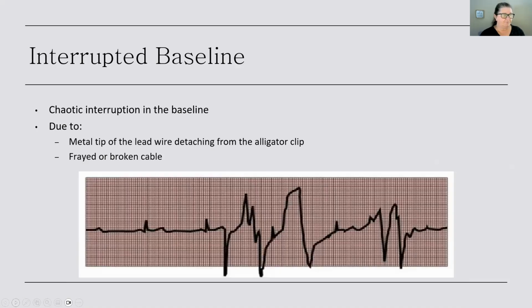Interrupted baseline is where you have a chaotic interruption in the baseline. See, it's going along just fine, and then this got all crazy. That's usually because the metal tip of the lead wire has detached from the alligator clip for some reason, or you have a frayed or broken cable. So that's why it's always very important to make sure that you're maintaining your equipment well and that you are paying attention to those things, checking everything out before you use it.